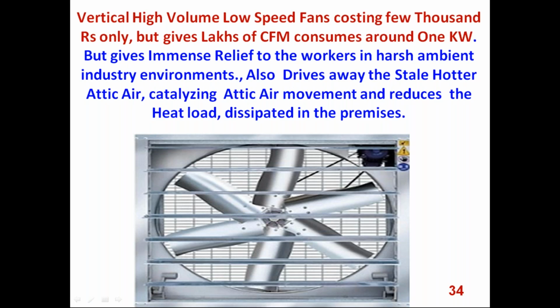This we have suggested to many of the industries where they go for attic ventilation, and where, in fact, when I went to Bangladesh for a World Bank study, we have come across so much of this. It's a 4 feet by 4 feet fan. This is used on all the attics and all the window level, sill level they are fixing it. It gives very low static pressure, Pascal is very low, but it will give lakhs of CFM at a few kilowatts only consumption, and this is able to maintain the supply to return air changes within the premises excellently well. We can think of it and we can suggest to the industry to remove the hot and stale air within the premises. Always the air needs to be recirculated in the industry. Next, please.